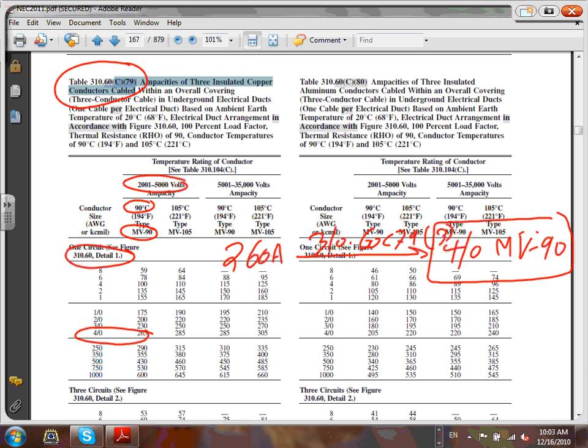These are basically 3 insulated copper conductor cables with an overall covering, 3 conductor cable in an underground electrical duct. I have 3 cables in 1 duct. That's one way of doing it. You can have 3 cables in 3 ducts; that's a whole different case. The most common one for medium voltage in this application is 1 big conduit underground with 3 cables in it. That's why I picked detail 1, not detail 2. Where does it describe the detail? Go back to page 155, and you can see how detail 2 is just 1 duct and multiple cables inside it. And I'm using, guys, a 3 conductor cable. There are so many applications, that's a good one.